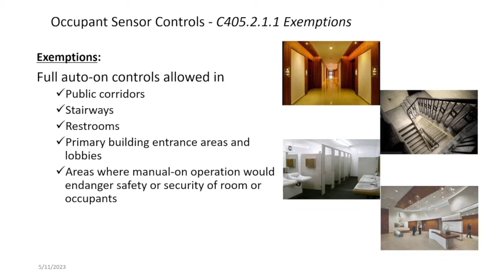Occupancy sensors are required in all these different spaces. I don't know if I have slides in here, but there's a couple places that we don't want automatically shutting off lights, and that's in corridors and stuff like that. But we can dim them in some of those places. And that's why the corridors are in there now. Corridors, stairways, restrooms, and stuff are exceptions to full auto on. Full auto controls with no manual allowed in these places.